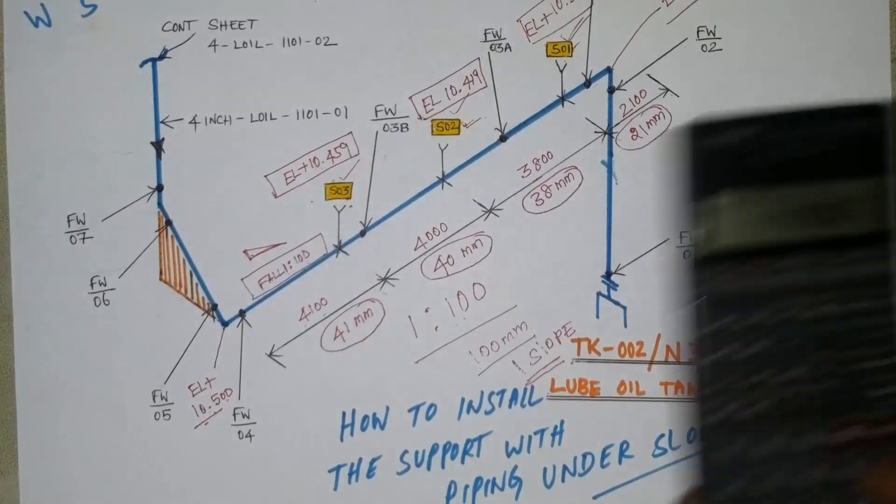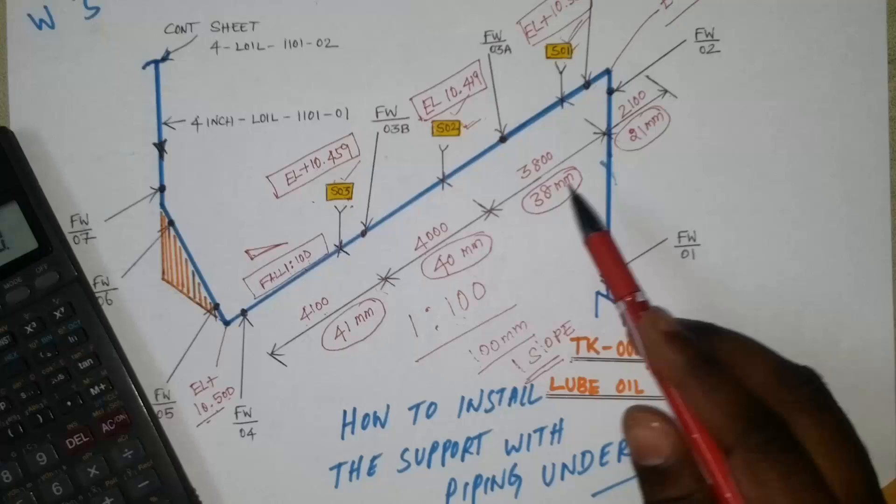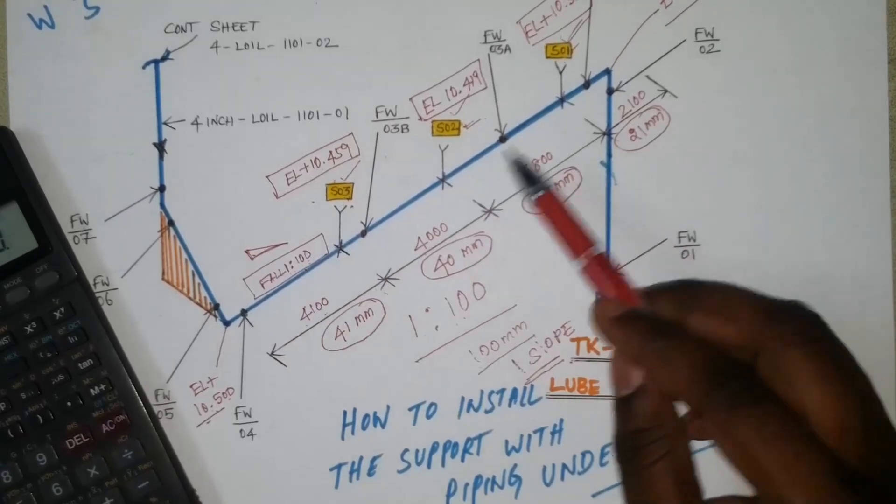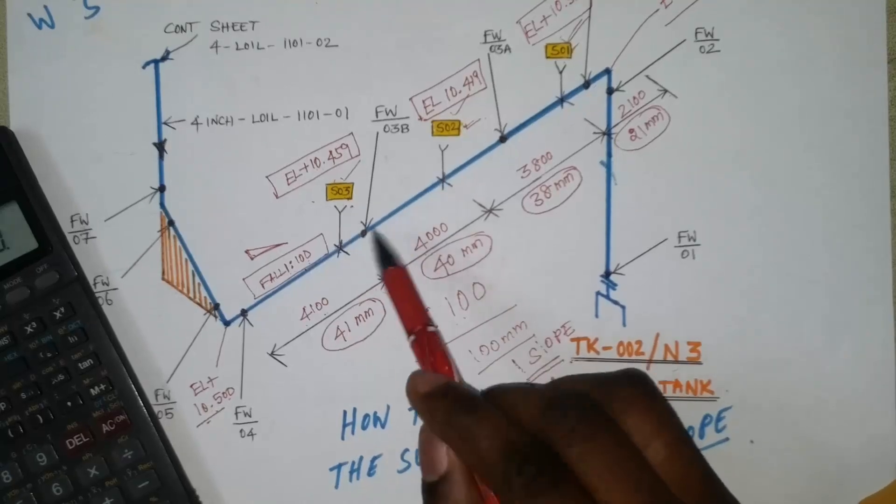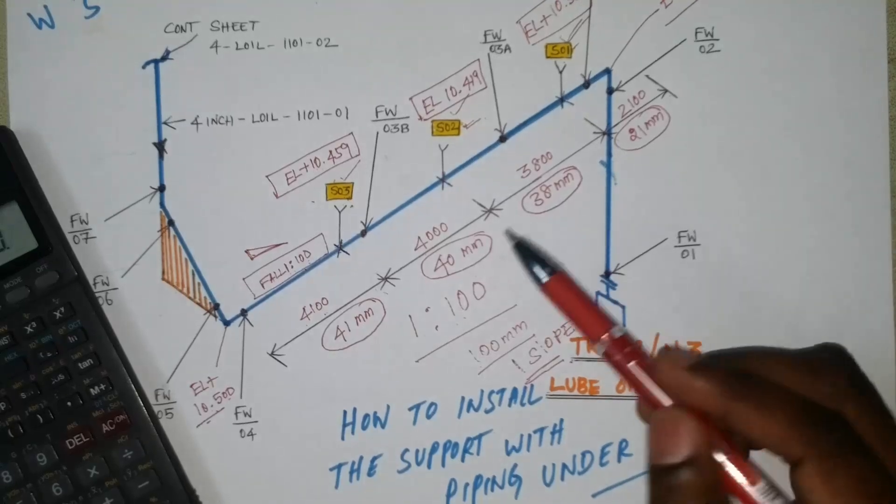Like that you have to install the support. In case the pipeline has slope, you have to calculate support elevation like that. Then by using water level, level tube like that, from the starting point you have to mark that support center.